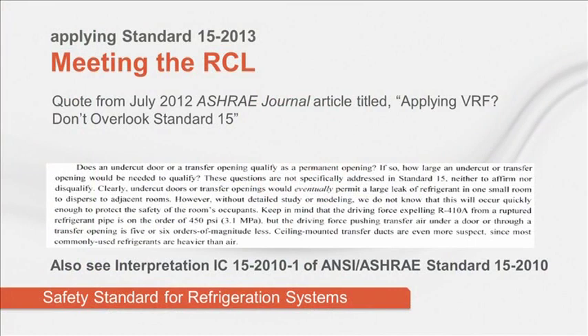Some sources have suggested that an undercut of the door is sufficient to permit the volume of the adjacent space to be included in the dilution volume. Others have suggested air transfer ducts from room to room or outdoor air ventilation systems are ways to increase dilution volume. The danger of this type of thinking is well stated in an ASHRAE Journal article written by Stephen Duda while he was a member of the Standard 15 Committee. I highly recommend the entire article, which can be found in the July 2012 edition of the journal.